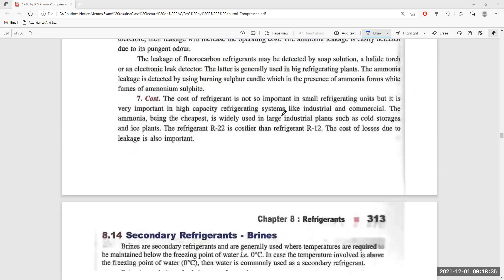Next, cost. Cost of the refrigerant is not so important in a small refrigerating unit because your amount of consumption is very less, but it is important in high capacity refrigerating systems like industrial and commercial systems. Ammonia, being the cheapest, is widely used in large industrial plants such as cold storage and ice plants. The refrigerant R22 is costlier than refrigerant R12. So the cost of losses due to leakage is also important.